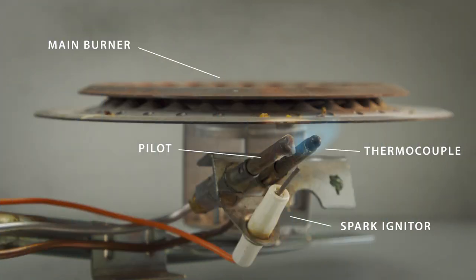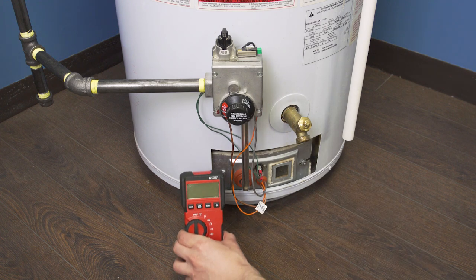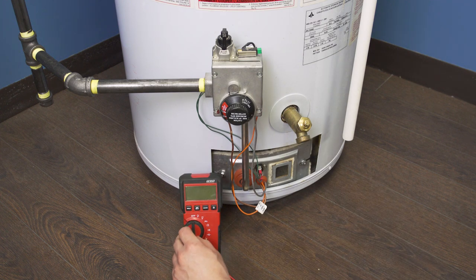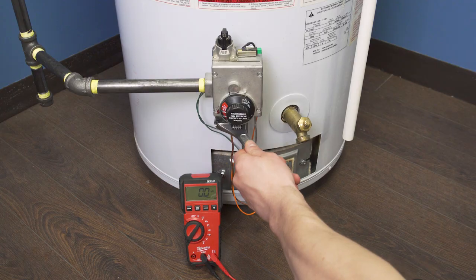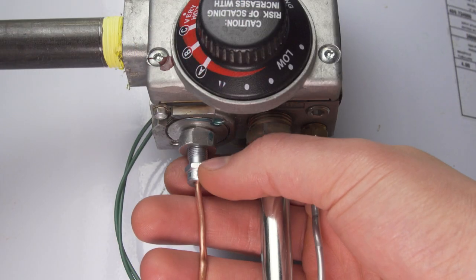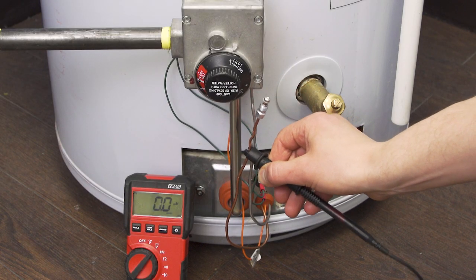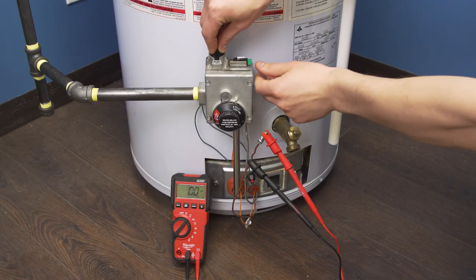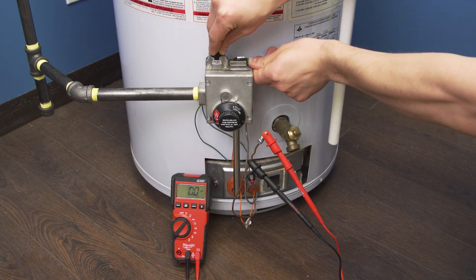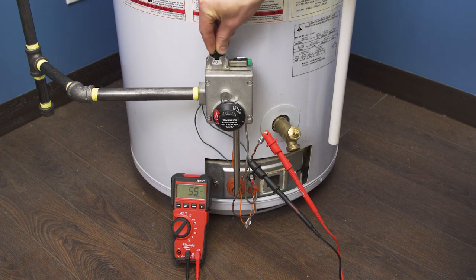The thermocouple voltage can be safely tested while lighting the pilot. First remove the bottom cover. Set the multimeter to the volts DC option. Use the adjustable wrench to unscrew the thermocouple from the control valve. Now connect the probes to the copper and to the end of the thermocouple. Light the pilot and hold down the button. The voltage should start to rise over the next few minutes as the thermocouple heats up.